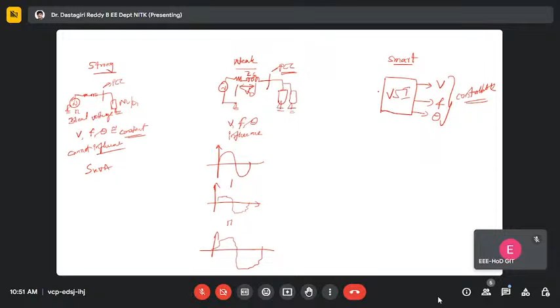That will be reflected. So for example, if you want to connect this to a strong grid, what will you do? You use something called a PLL to get the voltage, frequency, and theta of the grid, and use this information to control the voltage source inverter so as to match the voltage, frequency, and theta accordingly. Then you can happily integrate with the strong grid and keep exchanging P and Q.